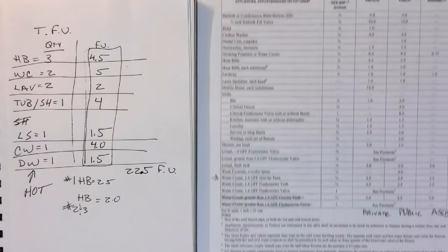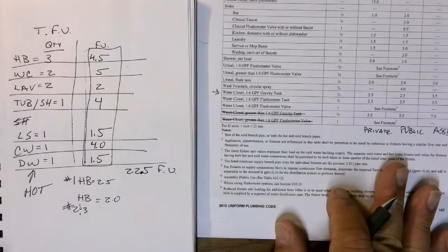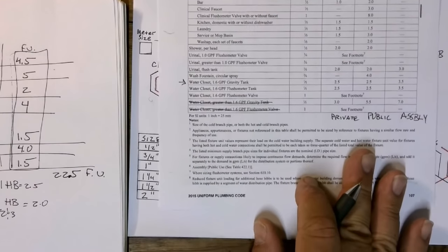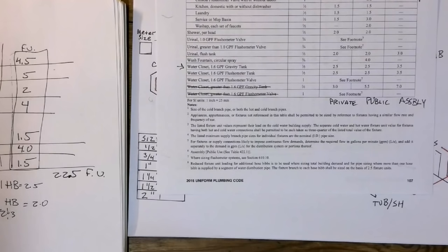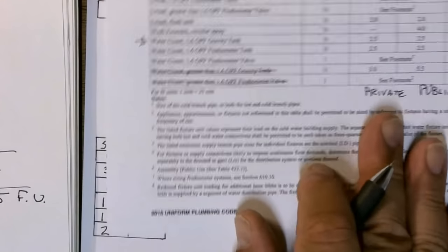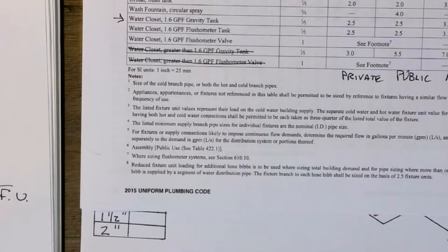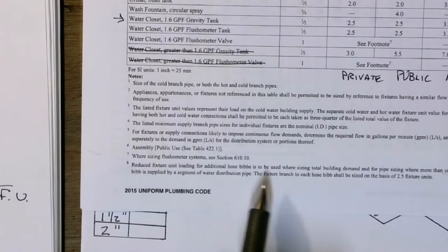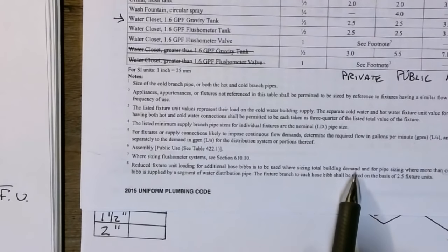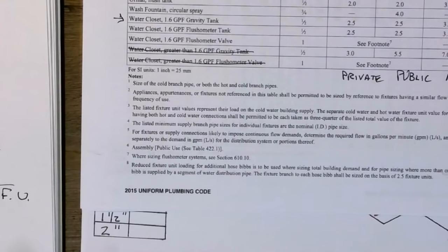I told you we would go to number 8 in the notes. Let's go to number 8 in the notes. We're going to blow it up too. So I want to make sure we get to read this and we understand it. Reduced fixture unit loading for additional hose bibs is to be used where sizing total building demand, which is just what we did, right? We just calculated our total building demand at 22.5 fixture units. It is to be used where sizing total building demand and for pipe sizing where more than one hose bib is supplied by a segment of water distribution pipe.